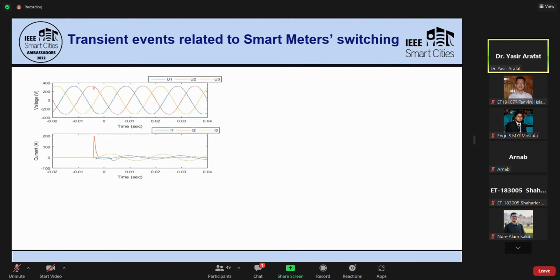However, for the second and third tests, we lowered the standard limit. The limit for a transient event could be plus or minus 50%, but we lowered it to plus or minus 25% to detect even small transient events, so that we could make sure we observed the power quality events very carefully.